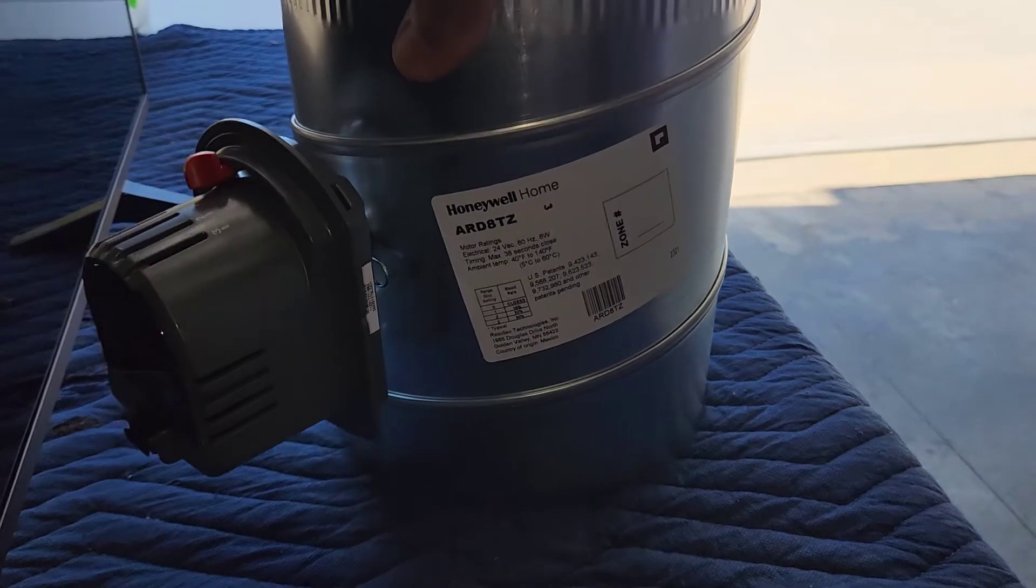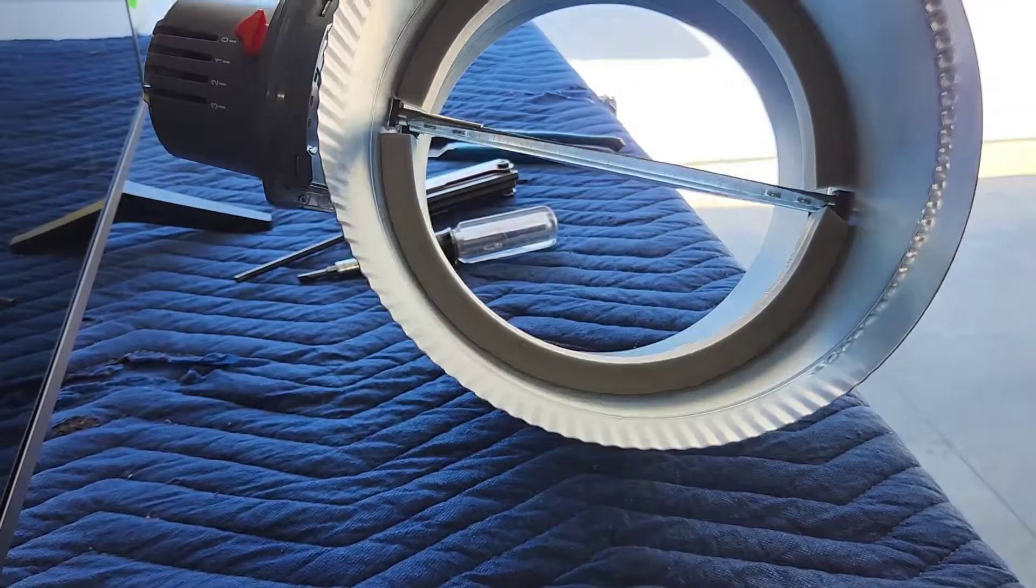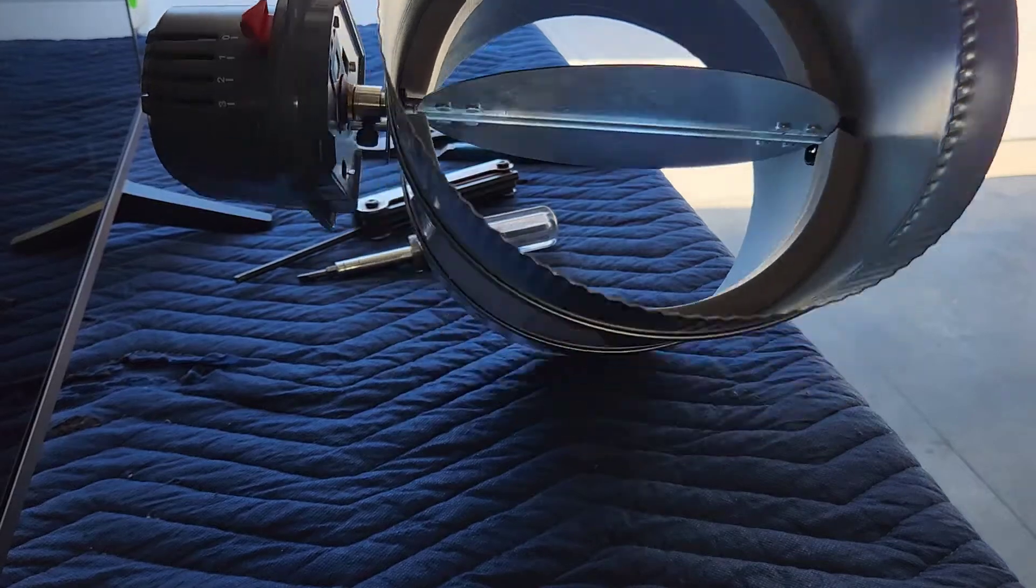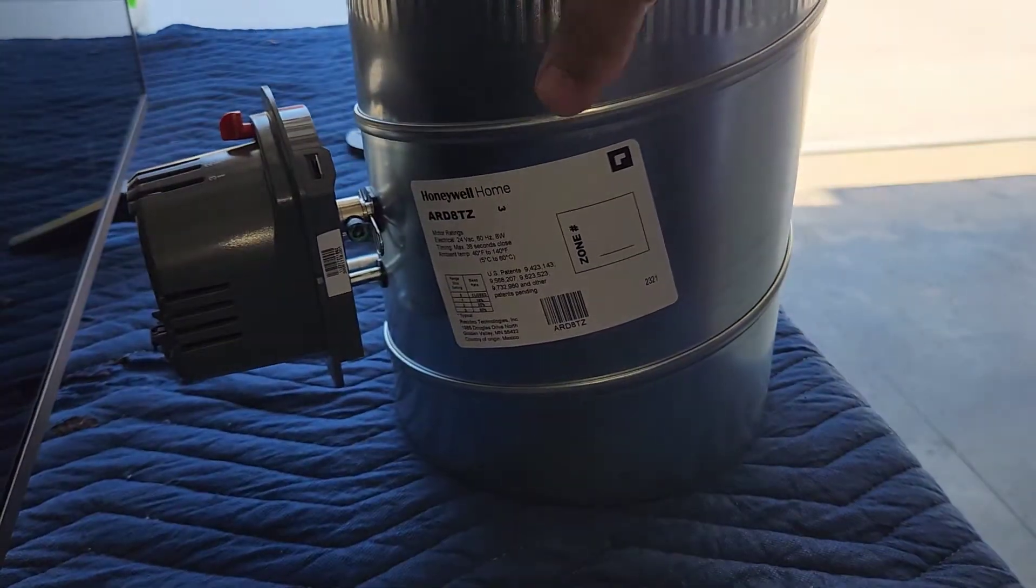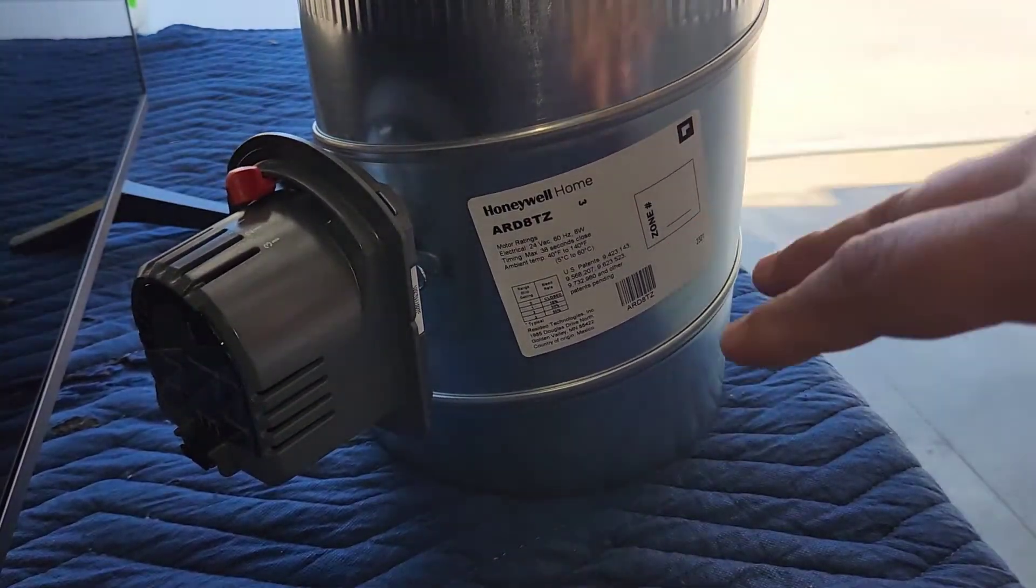But if you're using it as a fresh air damper, it's advantageous to have it to be normally closed where it powers open because that's how a lot of fresh air damper controls work.